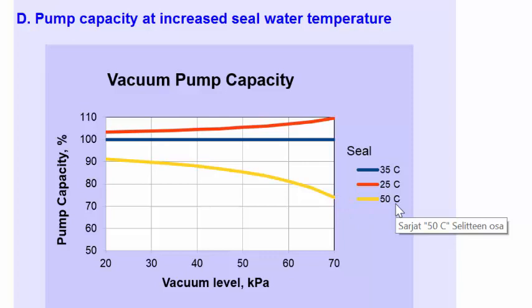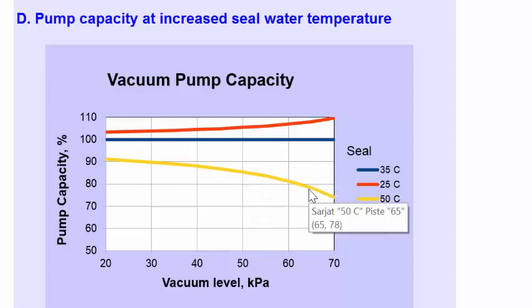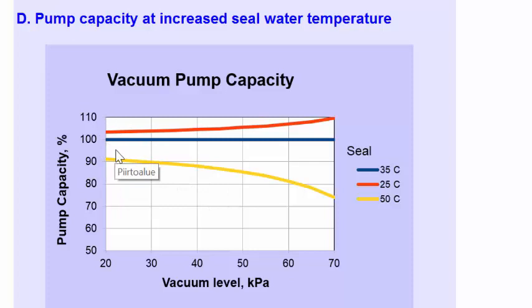If we look at the yellow curve and the situation where seal water temperature is 50 degrees Celsius — this can occur in some mills when sealing water is circulated through a cooling tower and there are problems causing insufficient cooling — the temperature of seal water can increase up to 50 degrees. In this situation, at a vacuum level of 50 kilopascal, we can see that the pump capacity is about 85% compared to normal running conditions. The capacity decreases more the higher the vacuum is. At lower vacuum levels, the effect of temperature on pump capacity is smaller.